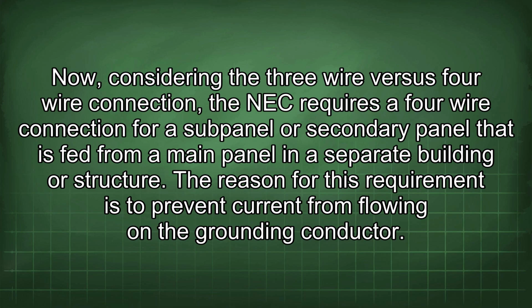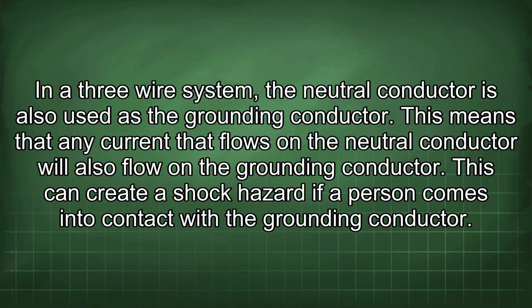The reason for this requirement is to prevent current from flowing on the grounding conductor. In a 3-wire system, the neutral conductor is also used as the grounding conductor. This means that any current that flows on the neutral conductor will also flow on the grounding conductor.